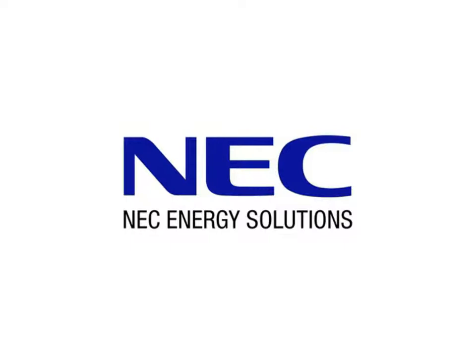Okay, so moving back to our questions now. Our next one asks, what is the size in megawatts of the frequency regulation market on the PJM? Total PJM market size for frequency regulation today is somewhere in the order of 700 megawatts. That's how much PJM requires to balance their grid, which, depending on the load, can be up to 100 some odd gigawatts of load that needs to be managed, and of course generation to match it.